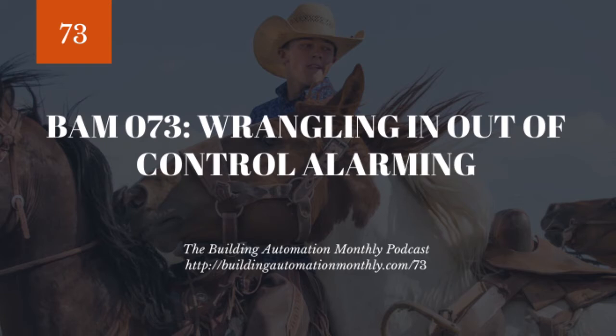They were getting filter alarms, low temp alarms, faulty switches - you've heard of flapping switches before. If you've been in the BAS world for any amount of time, you've probably heard the term. It's where a contact doesn't fully close, so it kind of opens and closes, opens and closes. This is notorious on safety contacts, on fan contacts. You have to go adjust their sensitivity - it's part of just a maintenance process.